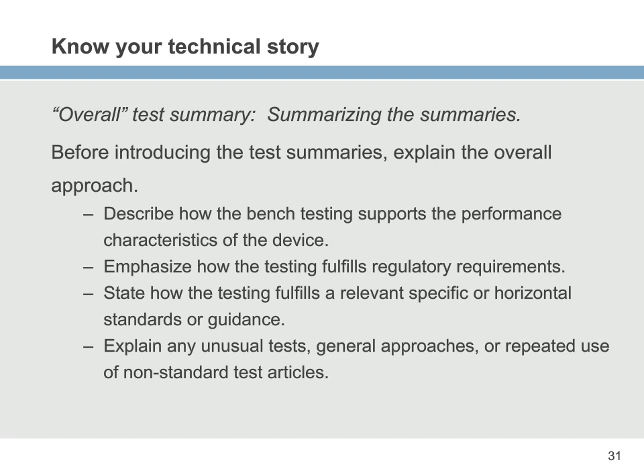So you also use it as an opportunity to explain unusual tests or general approaches or repeated use of non-standard test articles. So, for instance, we talked about, look, not all the time do you use a finished device. You may use a previous generation or a prototype. And if you have 5 tests that use the same prototype, rather than writing a paragraph in your test summary that says, and here's why that's okay, and here's how it differs, just put it in the overall test summary and say, hey, in 7 of the tests or 5 of the tests, we used a prototype, and this is what this prototype is about, and this is why it doesn't really matter for those tests. So that's just a communication strategy: just talk about it up front.